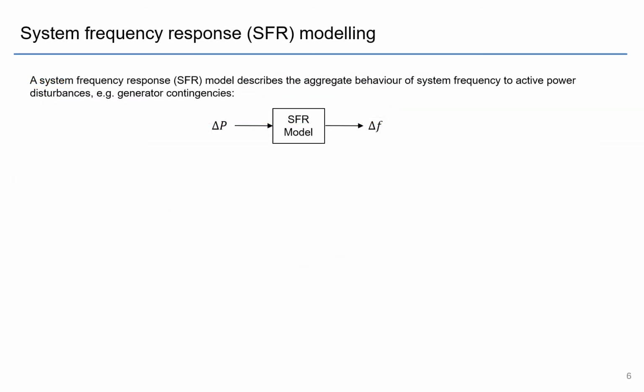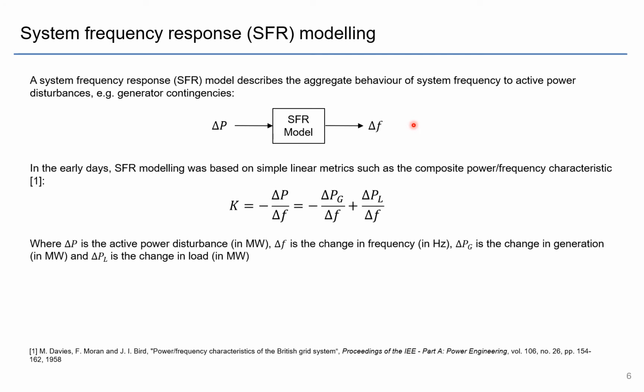A system frequency response model, or SFR model, basically describes the aggregate behavior of system frequency in response to active power disturbances, like a generation contingency. So you might have a disturbance here, a delta P, and just as an input to the model, you plug it in and you get some kind of frequency deviation at the end of that. So in the early days, SFR modeling was pretty simple, and it was based on some linear metrics. For example, here's the composite power frequency characteristic that Davies and the like did in Great Britain, back in the 1950s, late 50s.